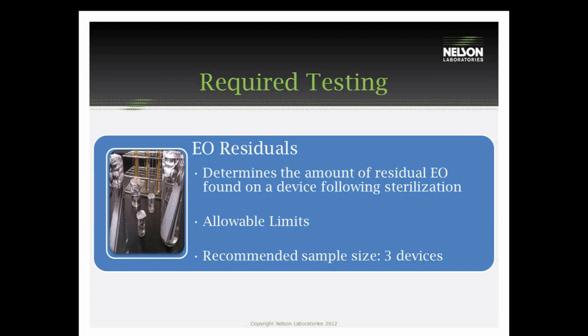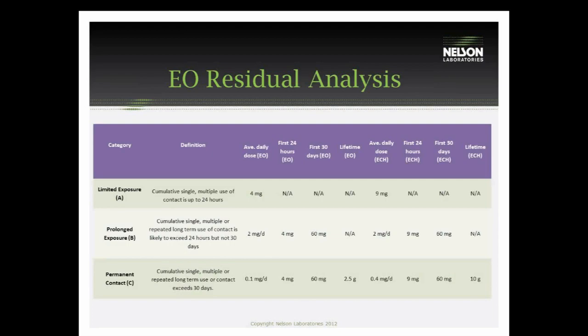For this testing, the devices will be immersed in an extraction fluid and extracted for an appropriate amount of time. The amount of time will vary based on the device. There are three product categories: limited exposure, prolonged exposure, and permanent. Limited exposure is any device used for less than 24 hours cumulatively — whether used once or multiple times by the same patient, it cannot exceed 24 hours total. Prolonged exposure is any device used for longer than 24 hours but not exceeding 30 days. Permanent contact applies to something that will have patient contact exceeding 30 days.